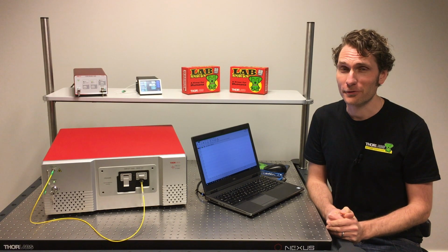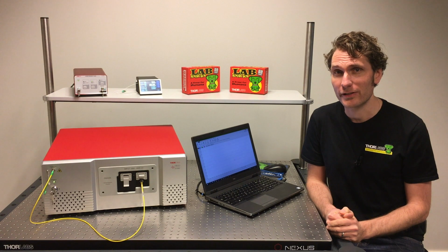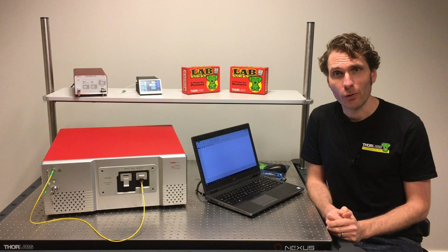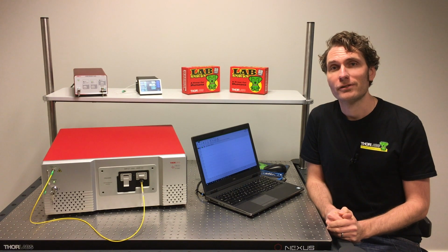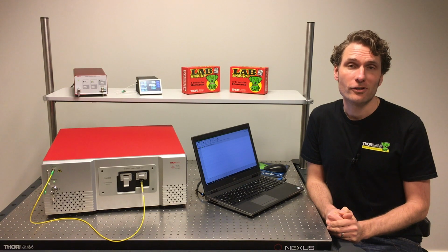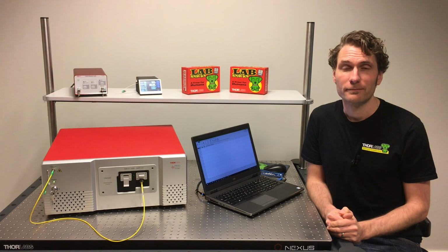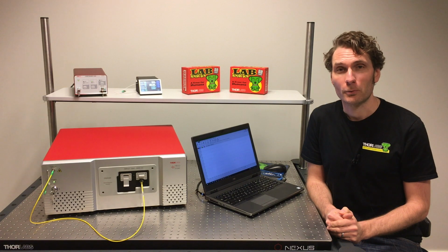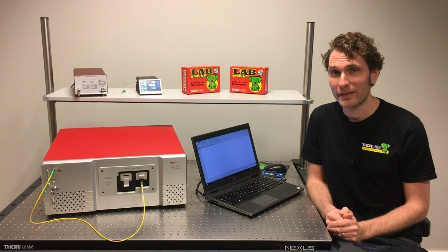Now, I don't expect you to do this very often because the calibration is very stable, but it's good to know that you can check the calibration instead of shipping the device over to a Thorlabs location every year. It's what we in Sweden call wearing both suspenders and a belt.